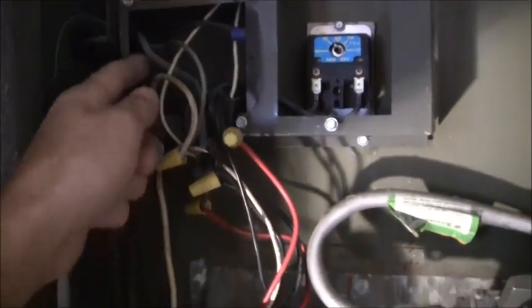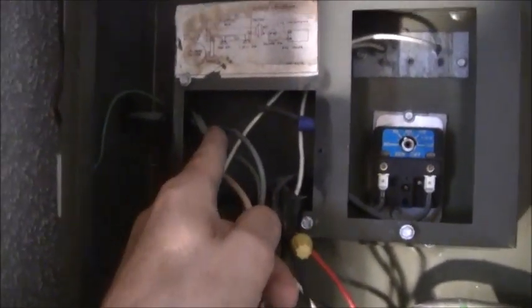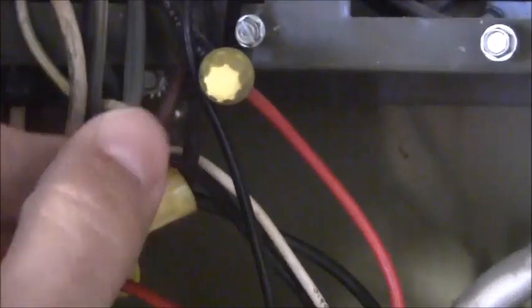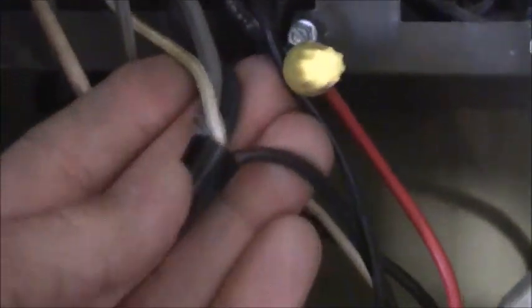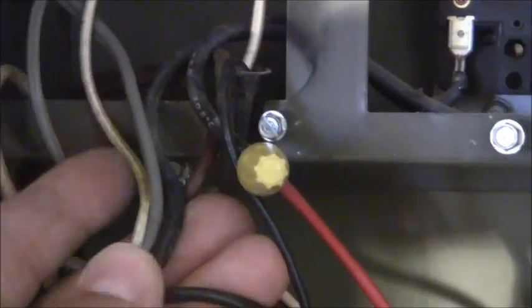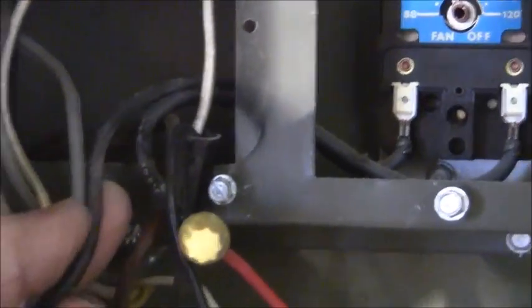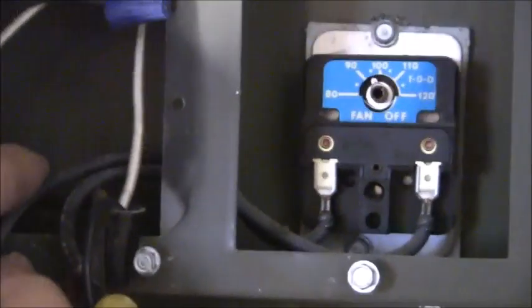Now, the way that this system operates is that over here, hold on a second. Okay, so you've got your plug here. Plug power, which is 110 volts, comes in right here, and then it splits off on the cord. One of the lines goes to all this white, so you know that's your neutral. This line over here is the hot. If I take that hot, it goes to this black wire nut, and then they disseminate off with the incoming wire and go off in a couple of different directions.